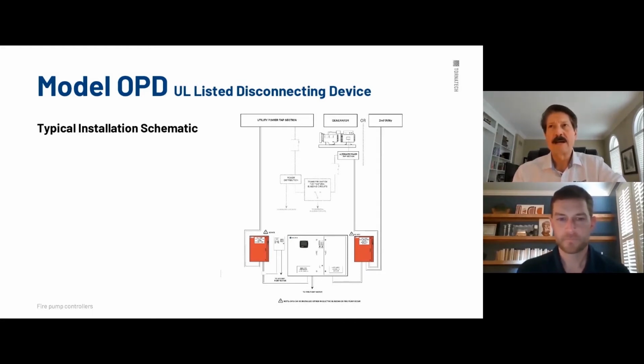Yeah, I mean, a lot of industrials have it, and they have a main. Again, it might not be the OPD, it might be a fusible switch, it might be in another room, and you have to physically go over there and lock it out. So I don't think there's anything by code, exactly what you said, Cole, that says it must be in a pump room. But when you get into a different location, there's other guidelines that you must follow. So to make it simple, which is what I always like, keep it simple. It's to your advantage to stay within 50 feet. Because I'm sure there's cable requirements if you're running through walls and what have you for fire, that you have to maintain. And if it's within the same room, within a short distance, you can save a lot of money compared to another location and having to run those cables through walls and so forth. But it's a very valid point.